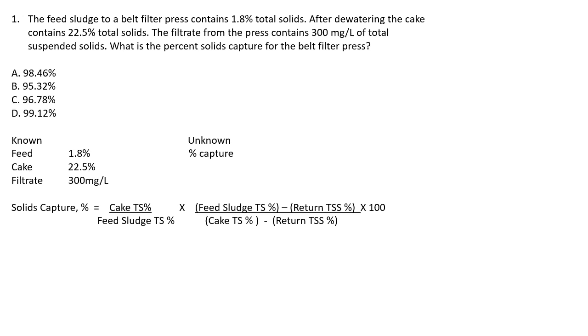We already have the feed percent and cake percent, but we need to convert the filtrate from 300 milligrams per liter to a percent. Remember: for belt filter press calculations, 1% equals 10,000 milligrams per liter. So we do 300 mg/L times 1% over 10,000 mg/L. The milligrams per liter cancel out, giving us 0.03%.